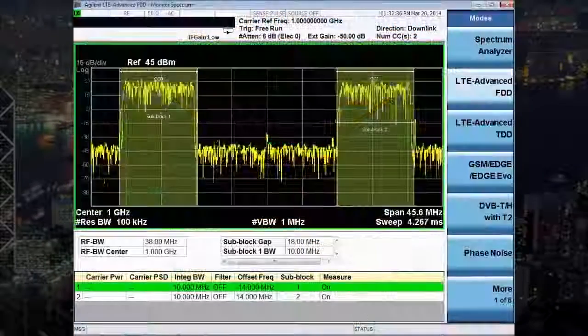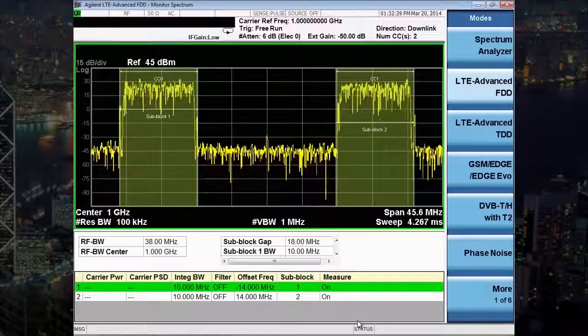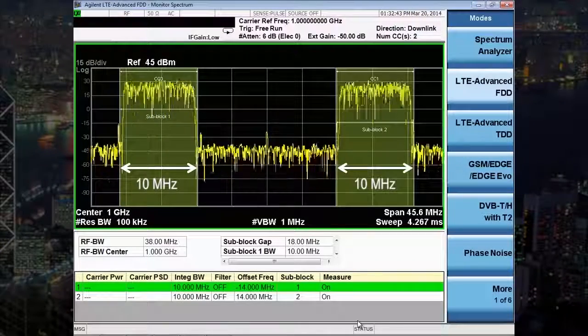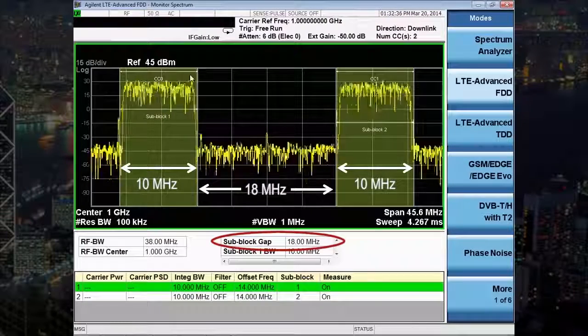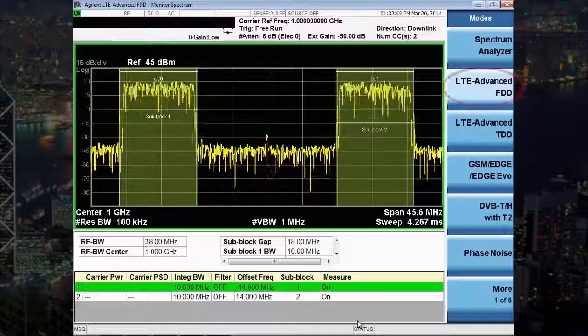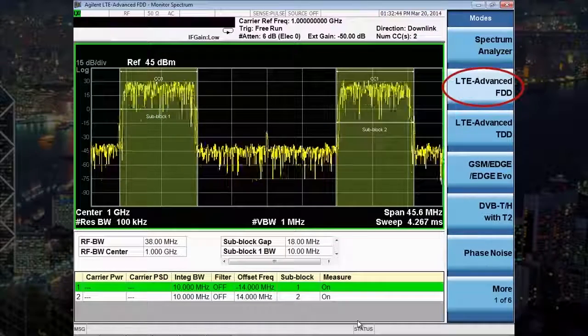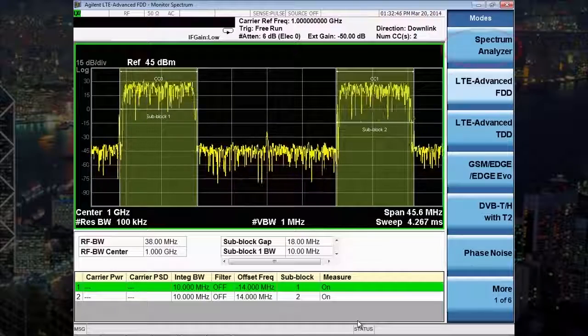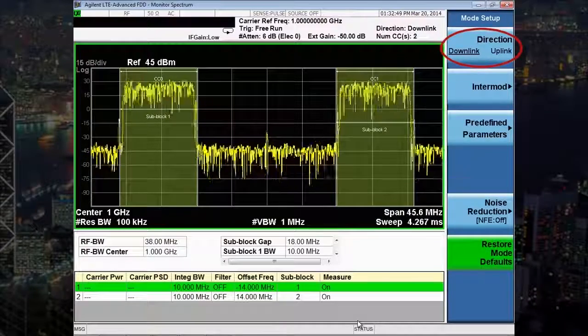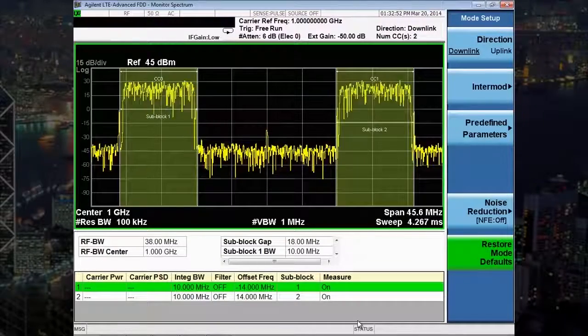So let's look at our first demonstration. The signal generated by the MXG vector signal generator is two 10 MHz wide component carriers with a sub-block gap of 18 MHz. On the X-Series signal analyzer, under the mode key, there are LTE Advanced FDD and TDD modes, but we'll focus on FDD for this demonstration. Both uplink and downlink tests are available, but I'll leave it on downlink for base station transmitter testing.